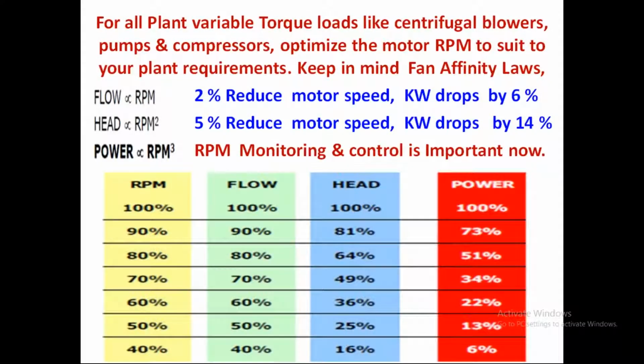Coming to the variable torque loads, RPM measurement is very critical, especially on all the blowers and all types of centrifugal pumps, maybe a centrifugal blower or an axial flow fan, definitely. At 90% of RPM, say a 1500 RPM fan with a 4-pole motor, if I am operating at only 1350, that is 90%, I am able to achieve savings of almost 27%. The power reduction is 27%, so energy saving is possible.